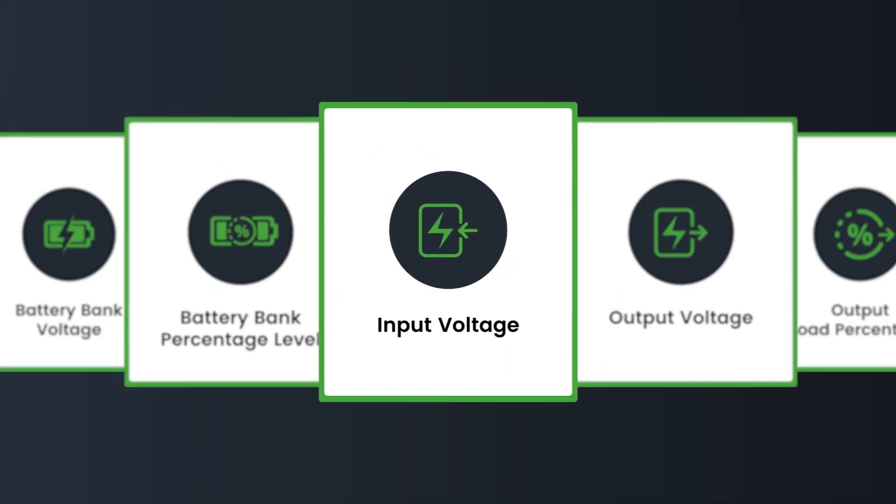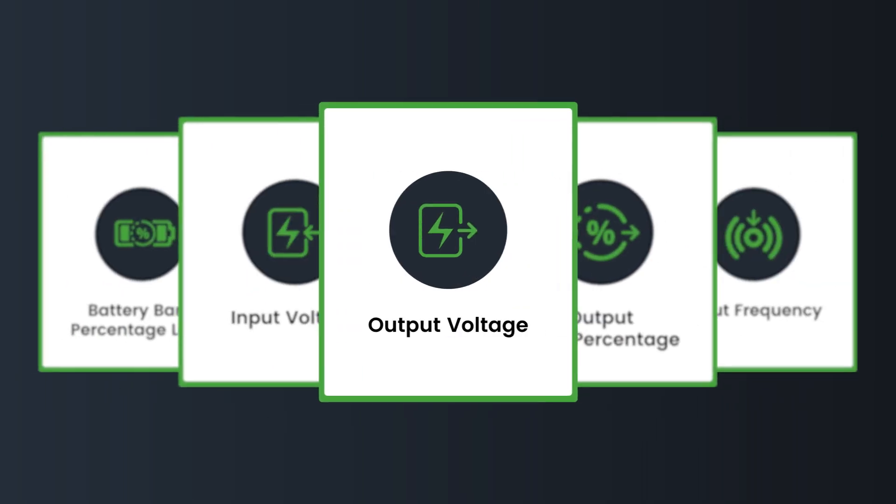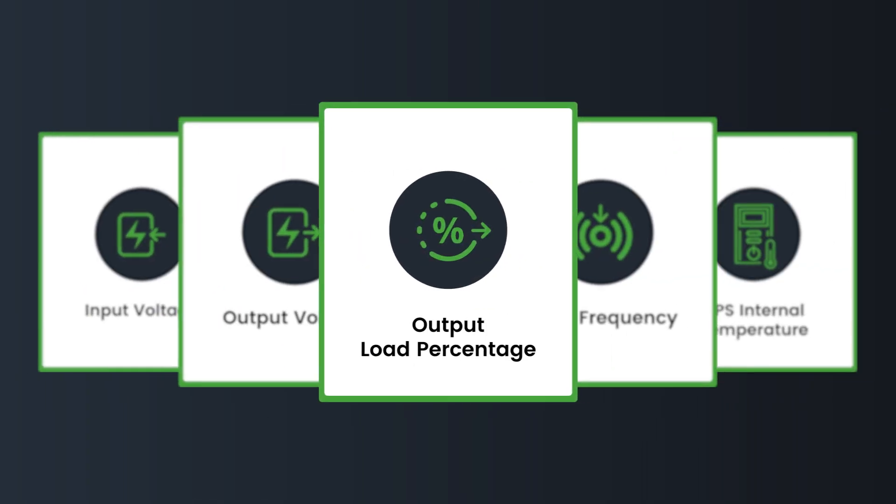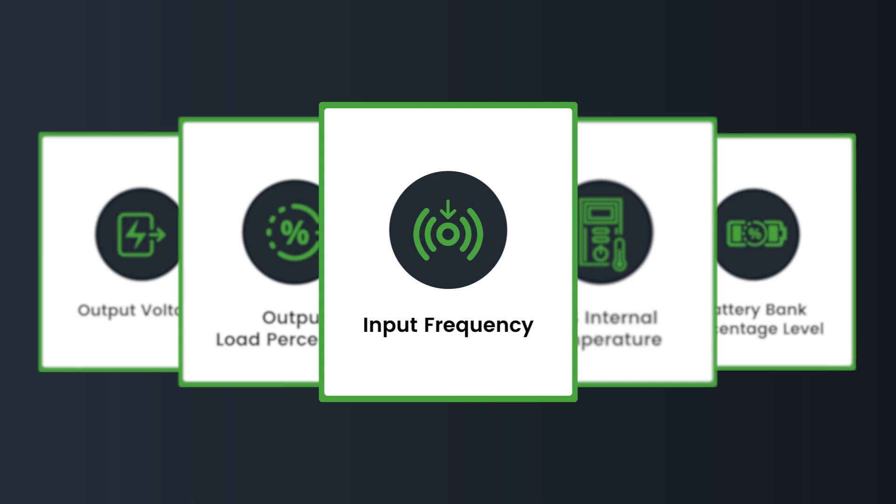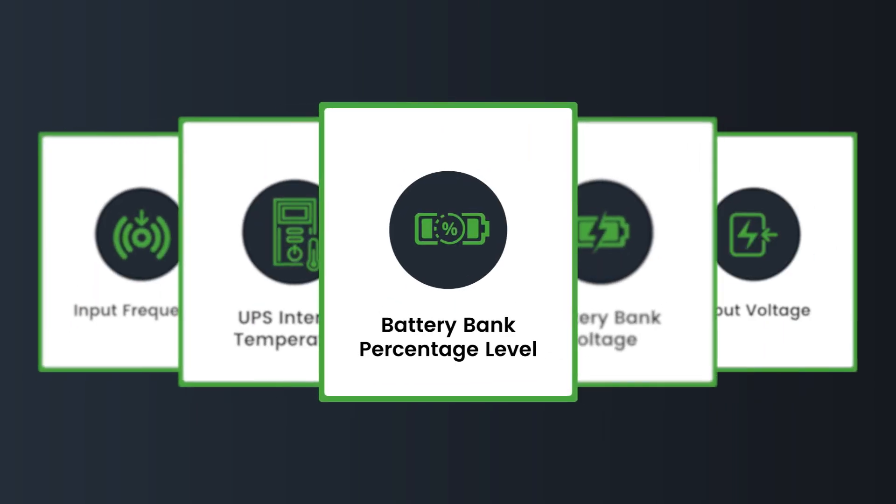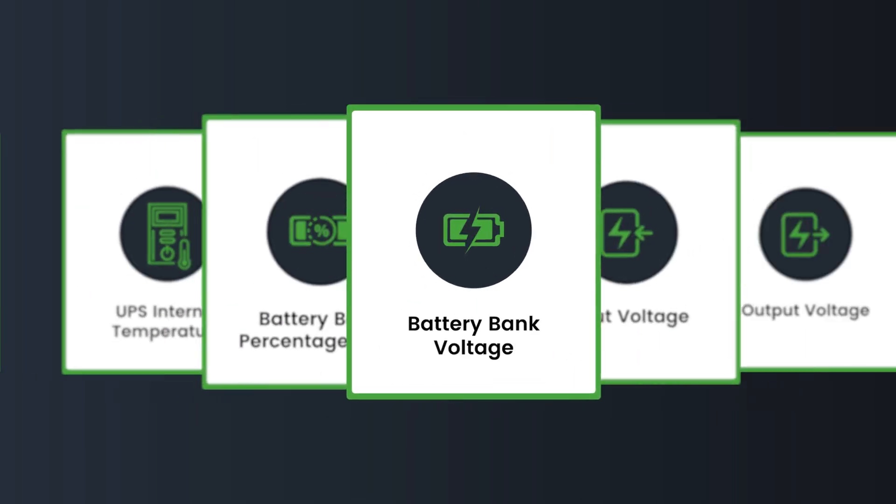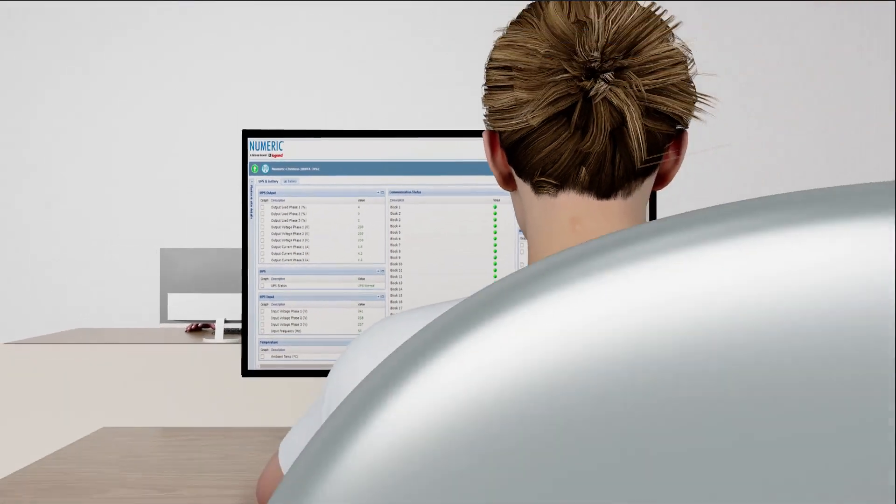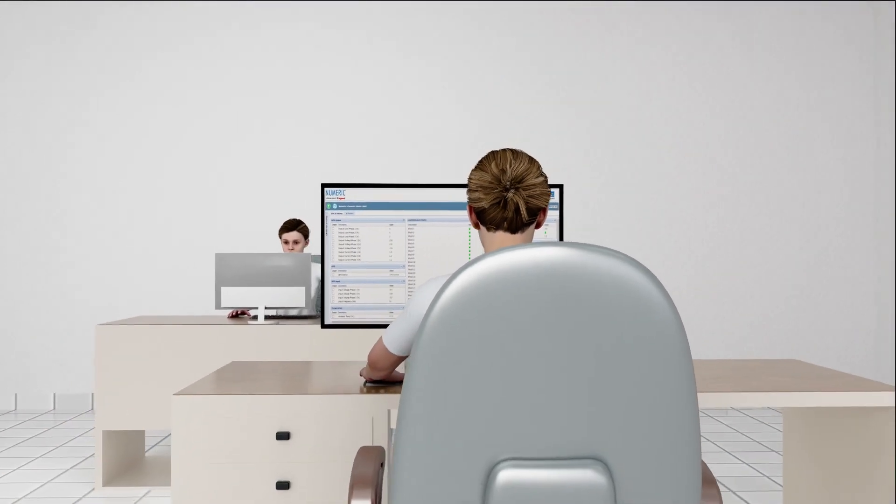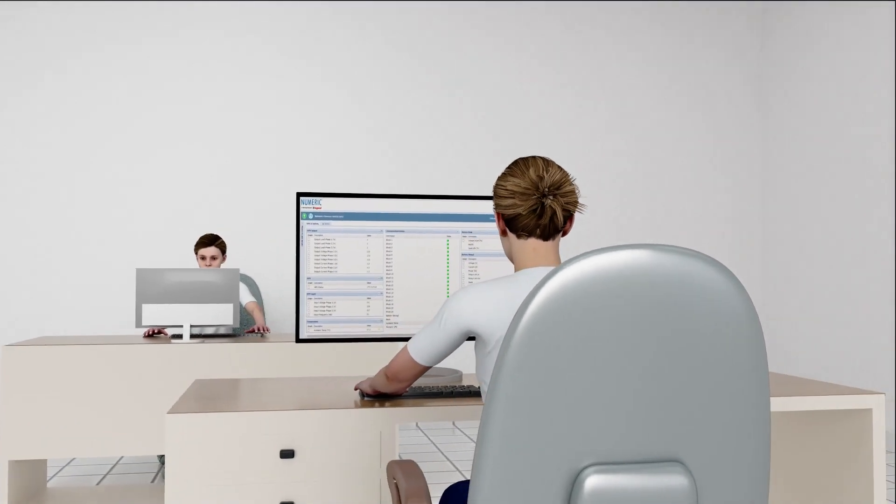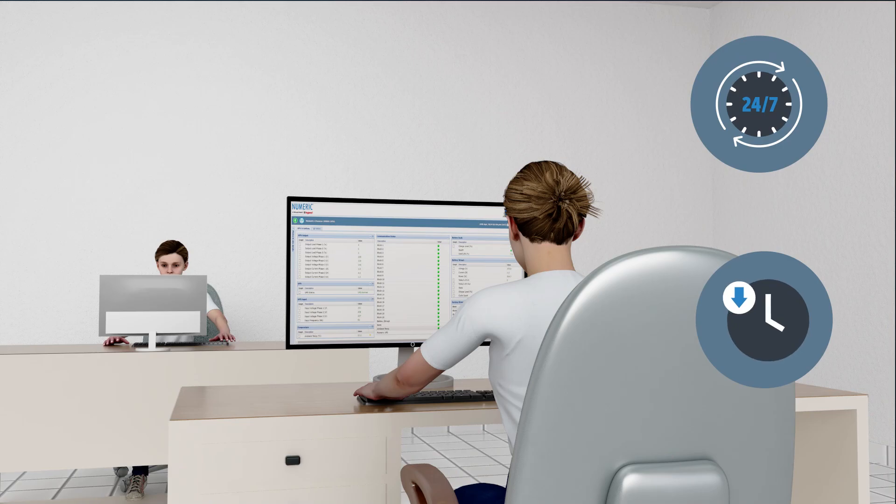Remote Monitoring System helps you achieve that by measuring input and output voltage, output load percentage, input frequency, UPS internal temperature, battery bank percentage level, and battery bank voltage. As a result, you can monitor your UPS's health 24 by 7 and reduce system downtime.